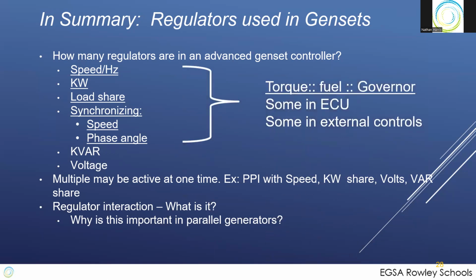And as a reminder, we covered this before, but the torque is controlled by the fuel, and that is the governor. Sometimes it's in the ECU, sometimes it's in external controls, but there always has to be something in control of the fuel, and they have to work with each other. So sometimes there'll be an external governor and an internal governor, and they have to work together so they don't have interaction between the two of them.